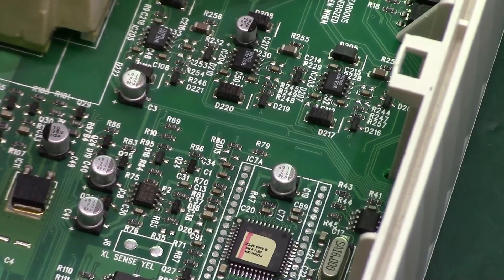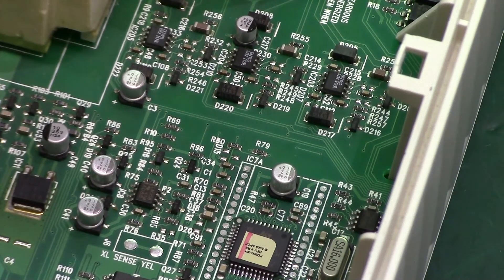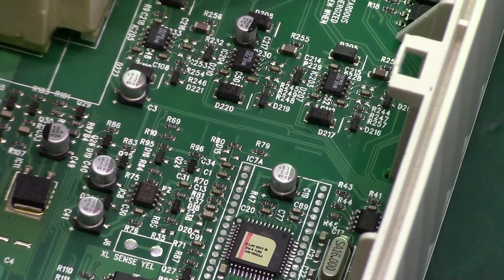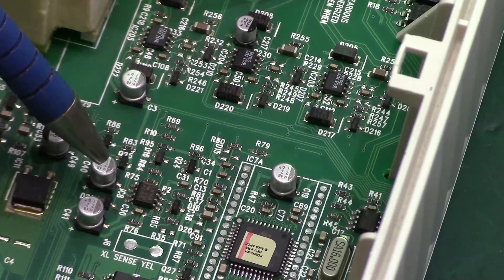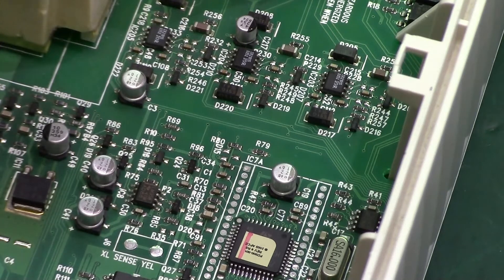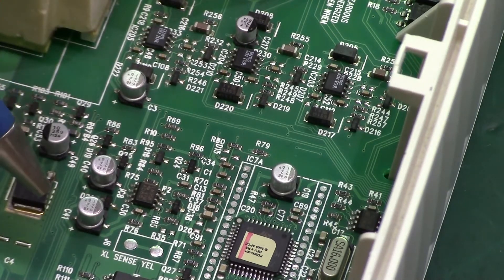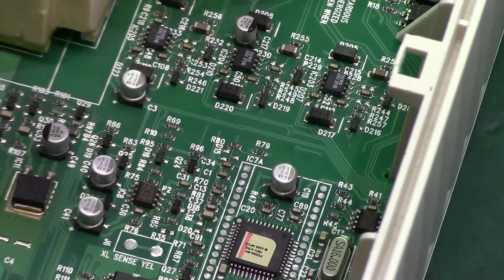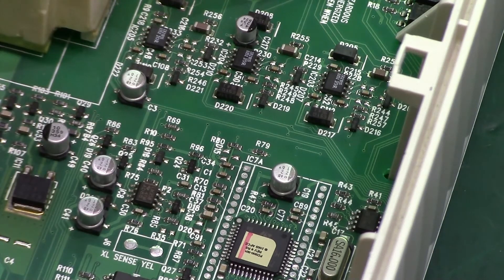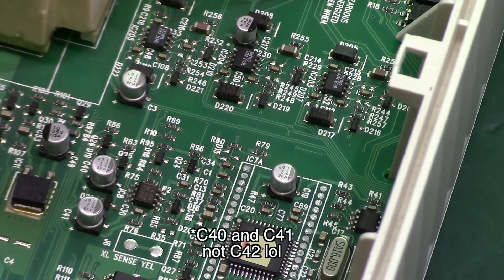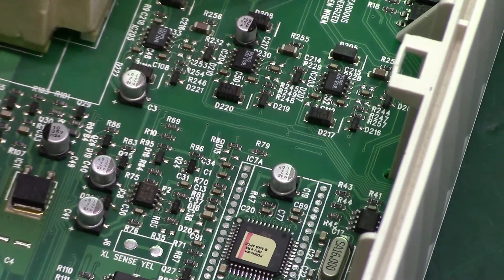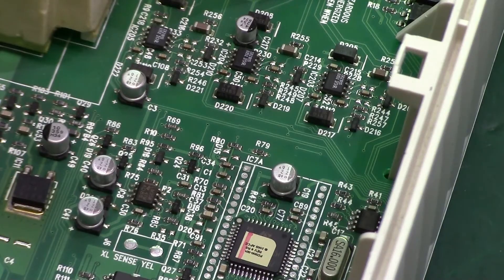So there's some research. Apparently, this is not an uncommon problem with these UPSs. And what a lot of people are pointing at is that some of these capacitors around the ADC, well there's no ADC on here, maybe on the microcontroller. But some of these capacitors, electrolytics, do actually dry out over time. And after that, the external voltage sensing no longer operates reliably, specifically C40, C41, maybe C60 as well. So I think it's worth desoldering a few of these caps and testing them out and seeing if they're any good.